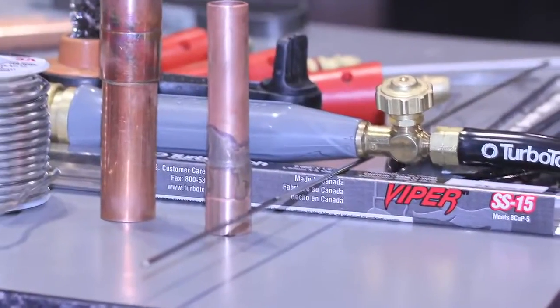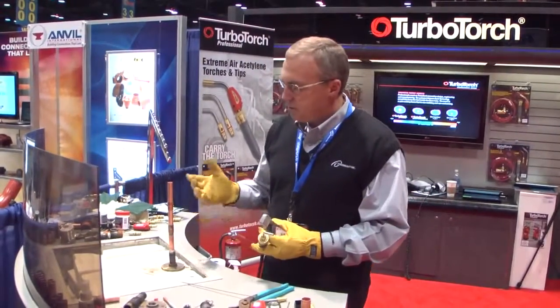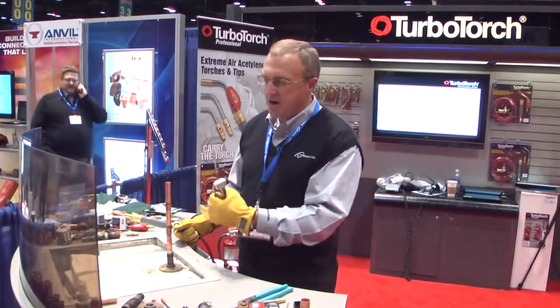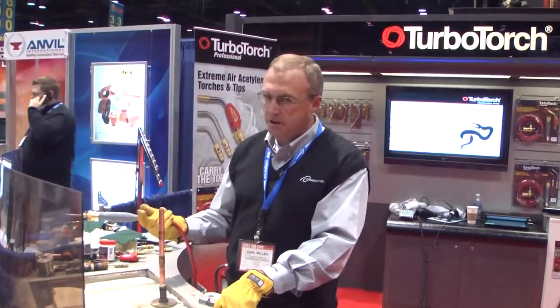The next process we're going to do is brazing — copper brazing, using a phos-copper rod. This has got silver in it; this is a 15% rod that's predominantly used in the HVAC industry. When you're brazing copper, this is for higher pressures. You have higher pressures going through ACR tubing and refrigerant lines as opposed to plumbing lines when you solder.